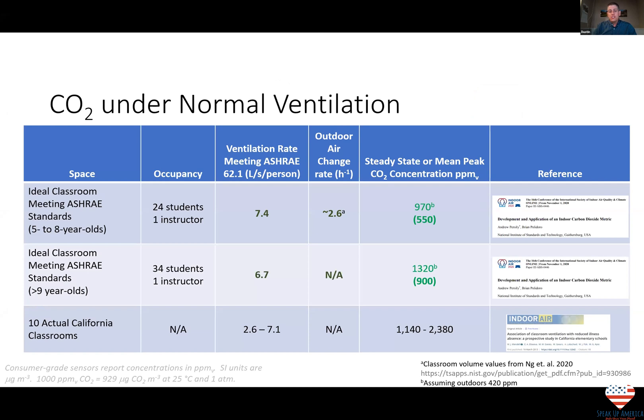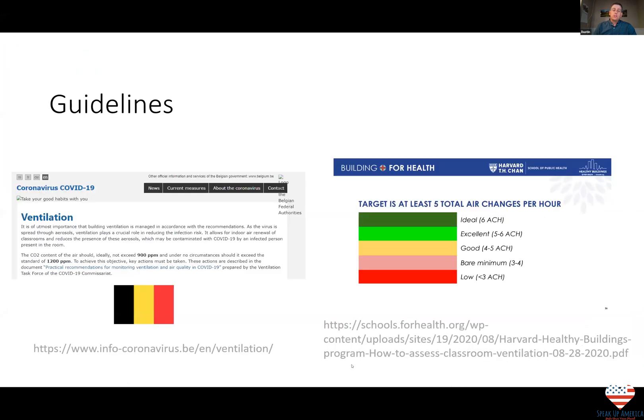ASHRAE is the North American standard organization for building operations, and it provides standard values that classrooms should be ventilated at in pre-pandemic times. ASHRAE recommends ventilation for classrooms with five- to eight-year-olds that would typically result in CO2 concentrations about 550 ppm above outside concentrations, or roughly 970 ppm, with an air change rate of about 2.6 for an average-size classroom. Since the pandemic, several organizations have suggested roughly doubling the effective ventilation rate to 15 liters per second per person, which would result in concentrations about 400 to 500 ppm above outside concentrations, or effective air change rates of about five to six per hour.